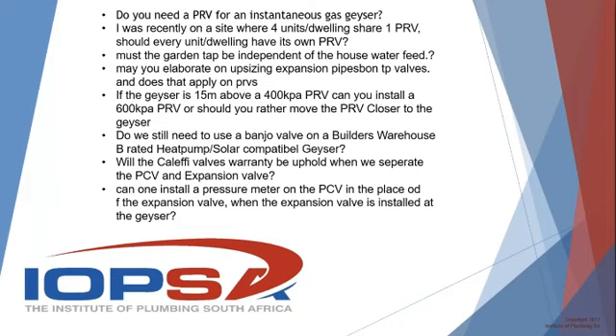So the question would be, do you use a banjo valve for the return on your solar system or the return on the heat pump? It would not be necessary if the geyser has a return port. At the back, it has a return port, in the same position as the anode is on the other side. But just adhere to whatever the heat pump manufacturer states in terms of when it goes into the geyser, if it has a little pipe that goes down to prevent the mixing. So it depends on where it goes into the geyser. But if it's this specific geyser that he talks about at Builders Warehouse, it would go into the center and it would suffice to work.